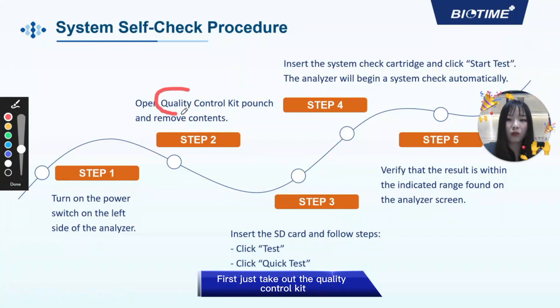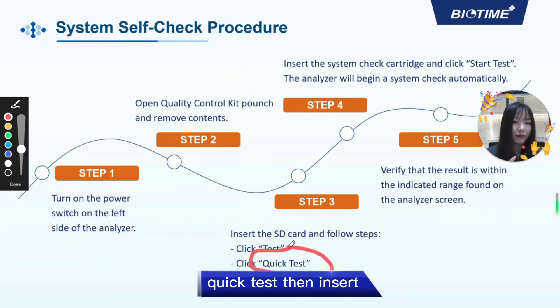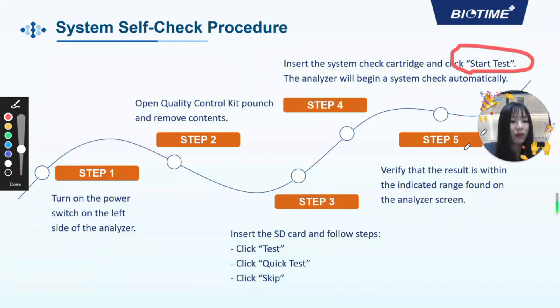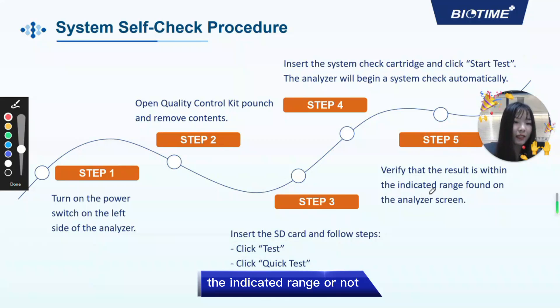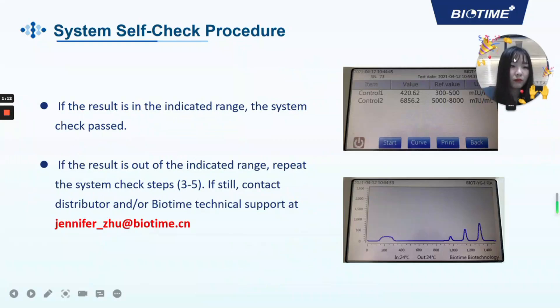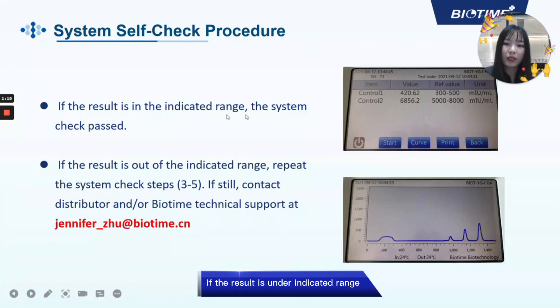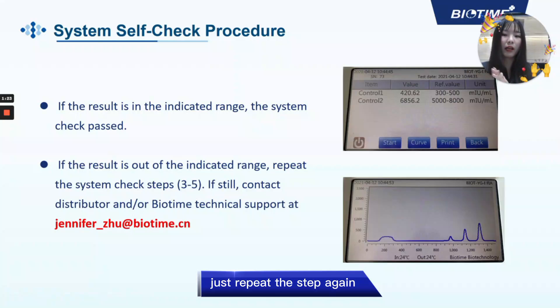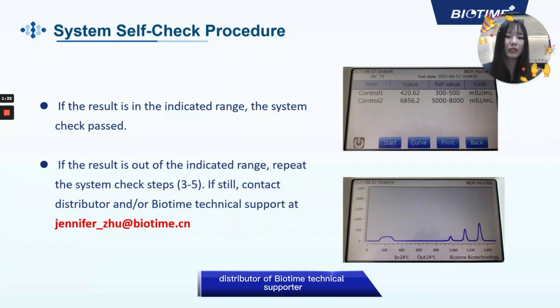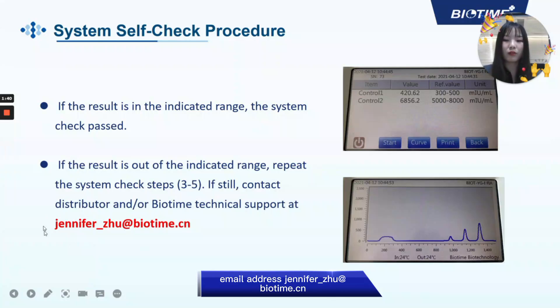First, take out the quality control kit and insert the SD card into the machine, then click Quick Test. Then insert the reagent into the machine and click Start Test. Then verify whether the result is within the indicated range. If the result is within the indicated range, the system check will pass. If the result is out of the indicated range, just repeat the steps again. If still out of range, you can contact your distributor or Biotime technical support. You can contact me at JenniferJu@BioTran.com.